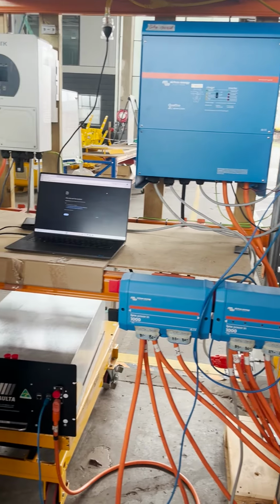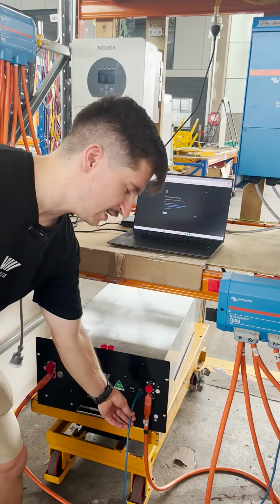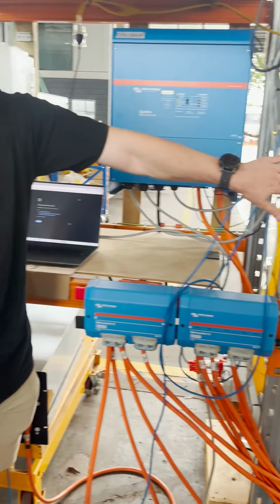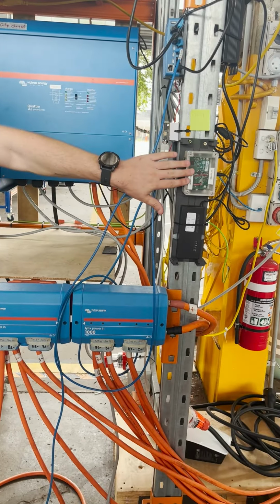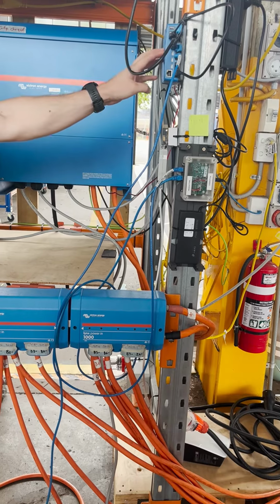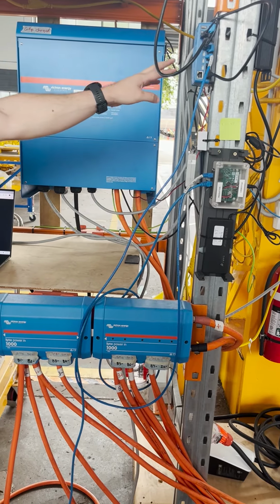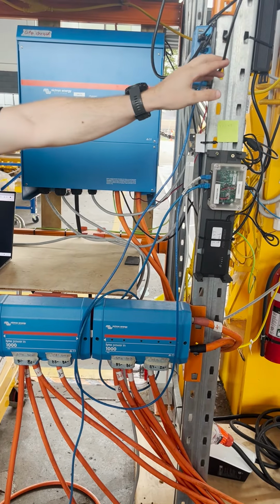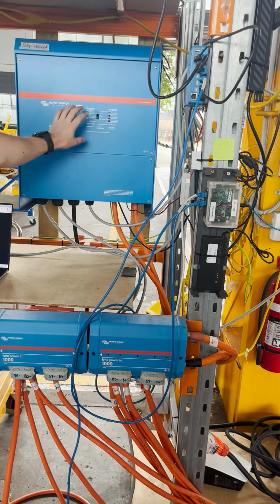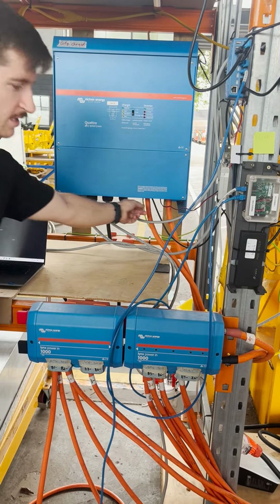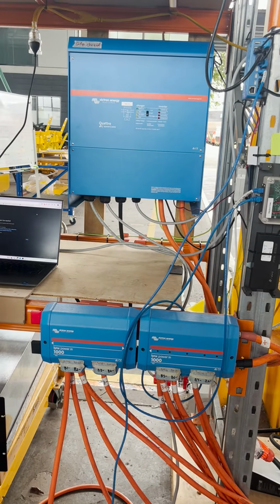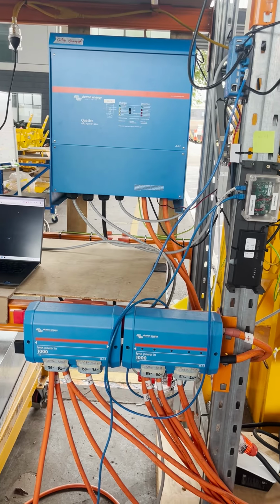From a comms perspective, we have a standard Cat6 or Cat5 cable that goes to our pack controller, and the pack controller uses the Victron cable to the Cerbo GX. The Cerbo GX also has a connection, a standard Cat5 cable, to the inverter's VE.Bus port.